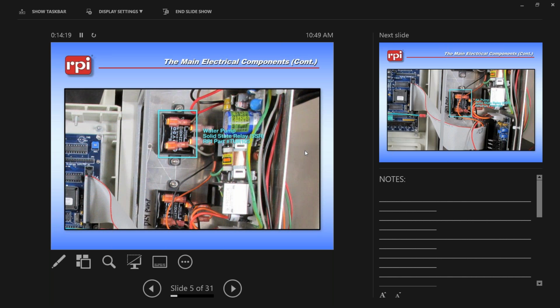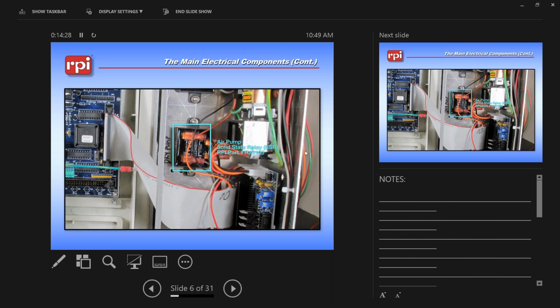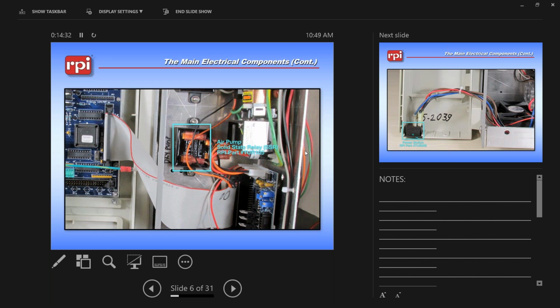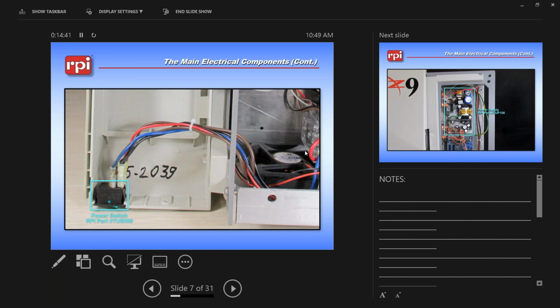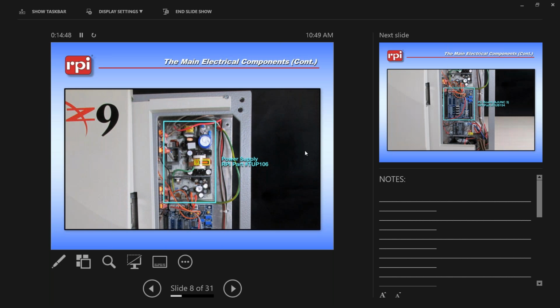Next, we have the water pump solid state relay. This, of course, just acts as an electronic trigger to allow your pump to run. Next down is, of course, the air compressor solid state relay. Again, just an electronic trigger to allow the air compressor to turn on. Your power switch, which of course allows power to go into the unit. Your power supply board, which at the top left of the board, that is your incoming 120 volts AC. At the bottom of the board, you'll see a black, orange, and red wire that is going to be your ground, your 12 volt line, and your 5 volt line DC that goes out to your adjunct board.